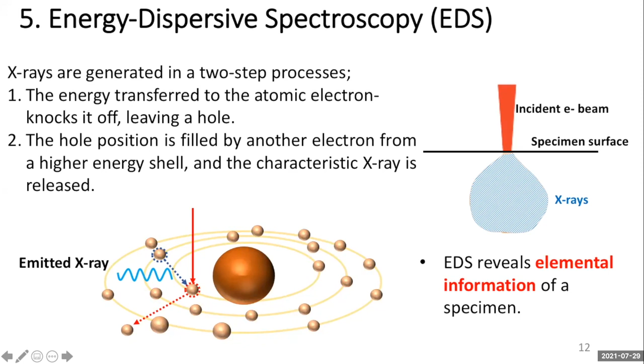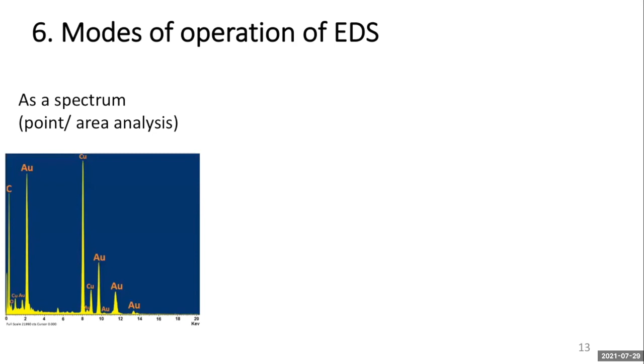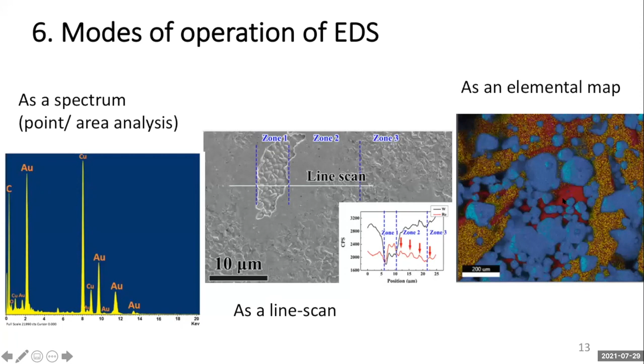The X-ray signals can be displayed in three modes. It can be displayed as a spectrum by using a point or area scan, or we can do a line scan so that we can identify the element variation along the line. So this kind of graph we can obtain along the line, showing how each element varies. Then as an elemental map, we can assign a different color to each element so that the image appears like this.